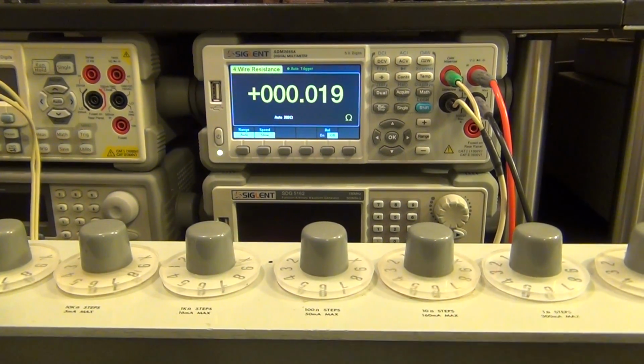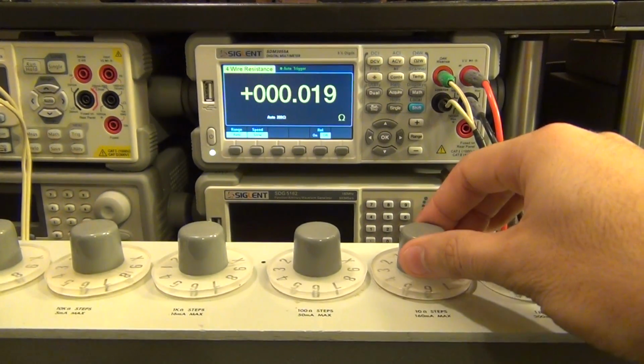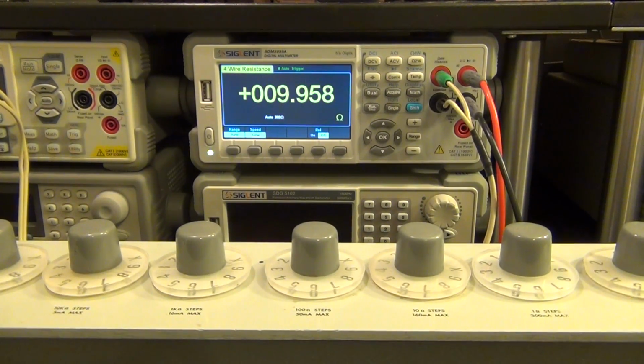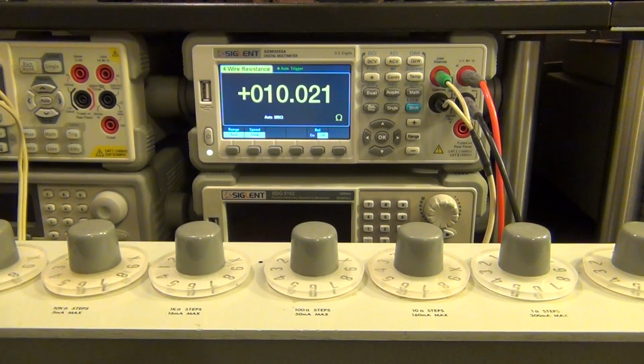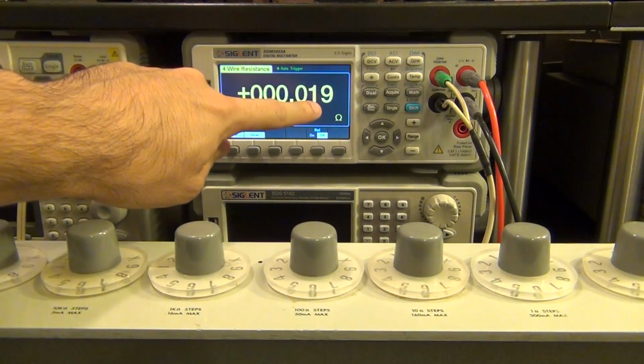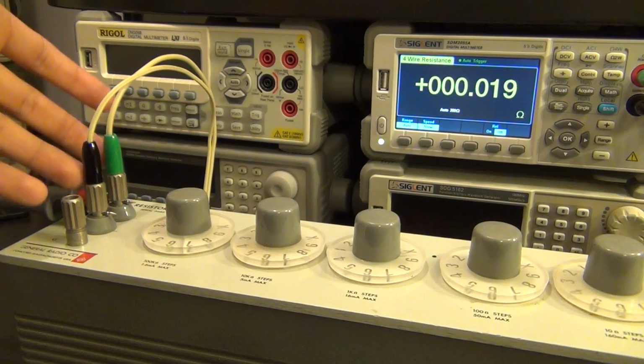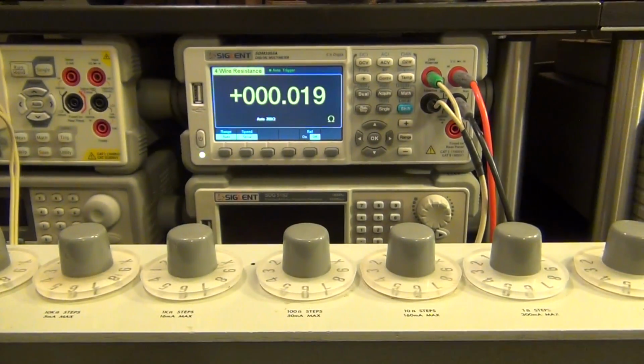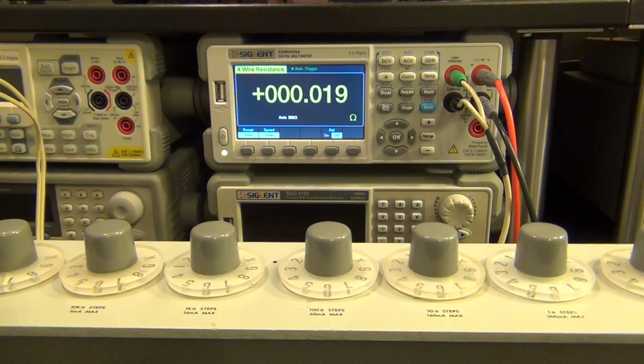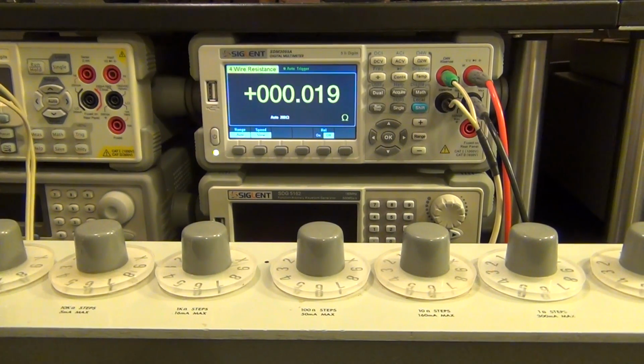If I dial in, say, 10 ohms, you can see it should give me 10 ohms, and it does, very accurately. If I go back to 0, the instrument tracks back exactly. This 19 milliohm you see is the difference from how these connections are interacting with each other, so that's normal — perfectly close to 0 as far as I'm concerned. 19 milliohms is very, very little.